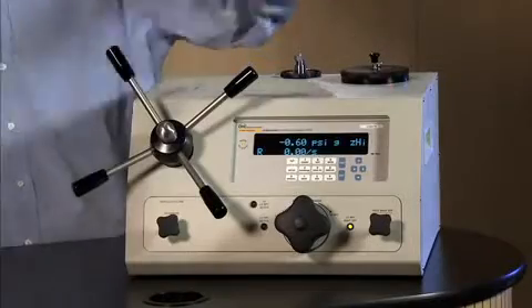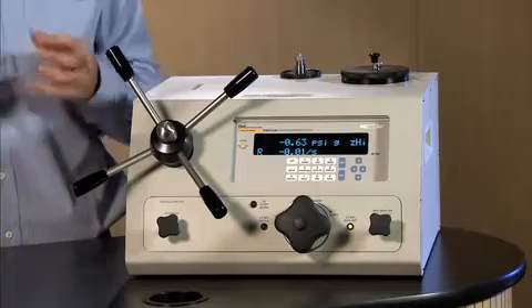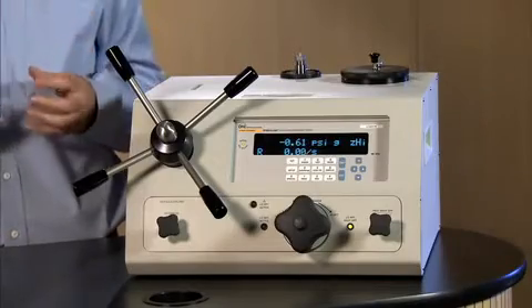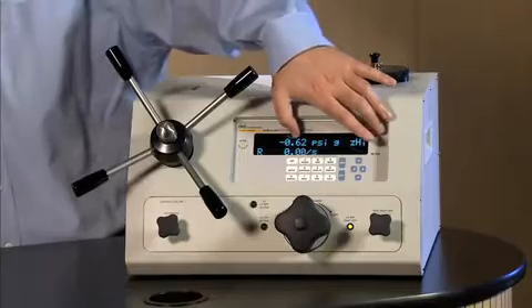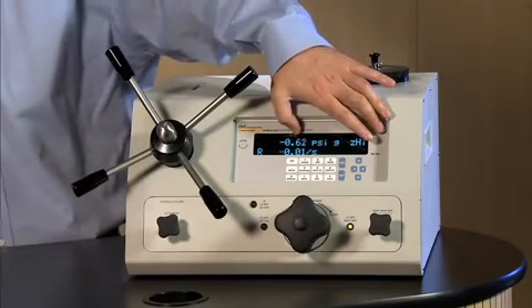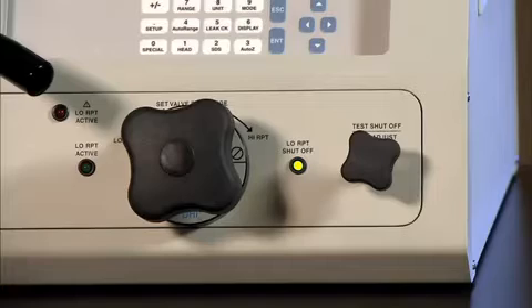The low pressure isolation valve only exists on E-DWTs that have 2 QRPT. QRPT stands for Quartz Reference Pressure Transducer. These are the reference measurement devices that are within the RPM4. The purpose of the isolation valve is to protect the low pressure QRPT from seeing the pressures that you will be achieving on the high QRPT side.